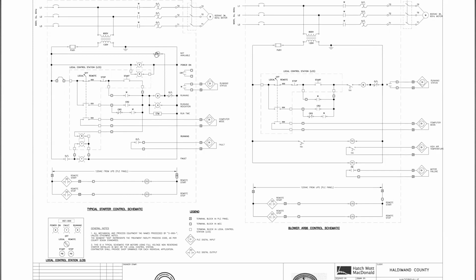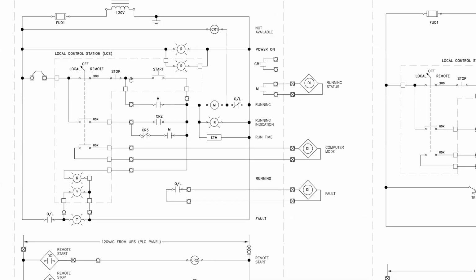So when you see CR1, what I'm looking for elsewhere in the drawing is a contact with CR1. CR1 here, there, that looks like the only CR1. So that looks like it's a signal potentially for a PLC. It doesn't show that it's a DI like the other ones. We've got a local off remote switch, where in local, the start and stop push buttons will run the system. The start and stop push buttons turn on M. M looks like it seals itself in around the start button.